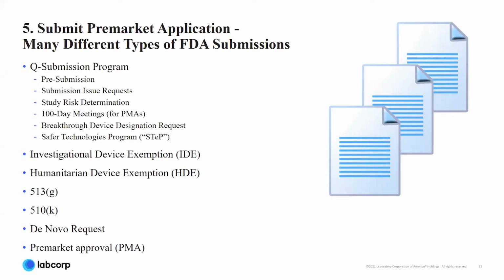And then it gets into step number 5, where we actually submit that premarket application. There are lots and lots of different kinds of submissions that you can do with the FDA. We talked about the 510(k) and the PMA already, depending on the risk classification of your device. But there are other ones. FDA really recommends the use of what's called the Q-Submission program. This allows you to get feedback on maybe a test plan or a clinical protocol or all kinds of different things, in a pre-submission, before you actually submit the 510(k) or a PMA. It really just helps ensure that what you're going to submit is what FDA would need in order to clear or approve your device.